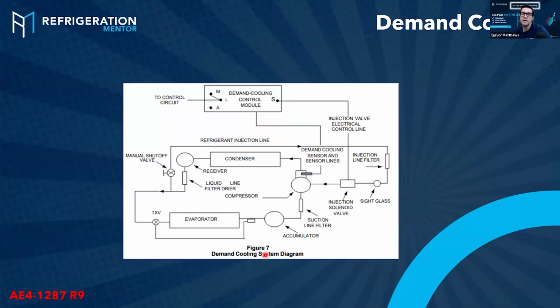Okay, let's dive a little bit into this demand cooling module, what it is. Honestly, you've got a controller. This controller has a sensor on it. The sensor goes into the head of the compressor or into the body of the compressor, depending on the design, because if it's a 3-cylinder, 4-cylinder, or 6-cylinder compressor, it's going to be different. Then you have an injection valve, which you need to take from your liquid line. So you have liquid refrigerant come from your liquid line. You have a T, and that liquid's going all around. Hopefully, you have a sight glass and inline filter. A lot of times you don't. You don't have a manual shut off, and then you have the injection valve.